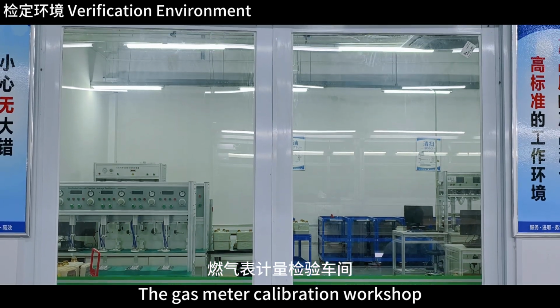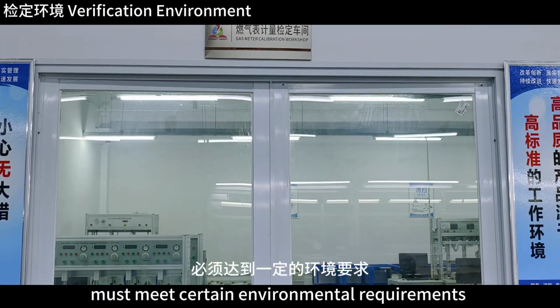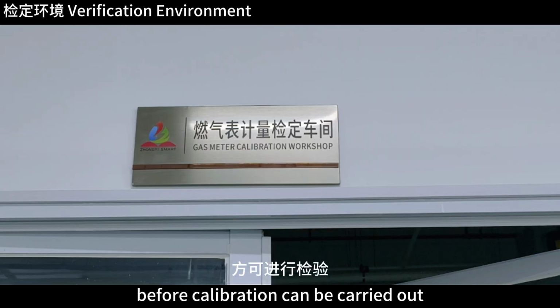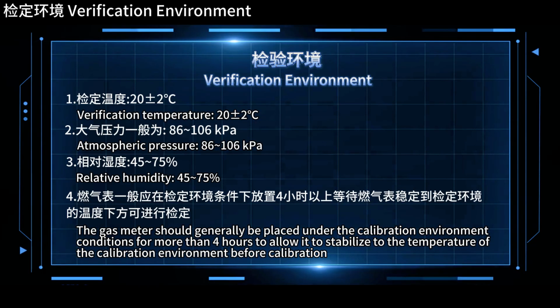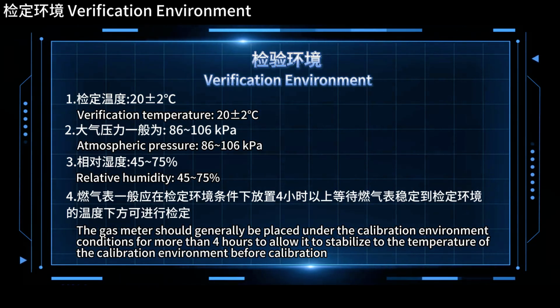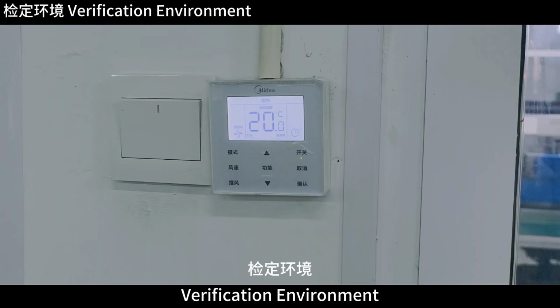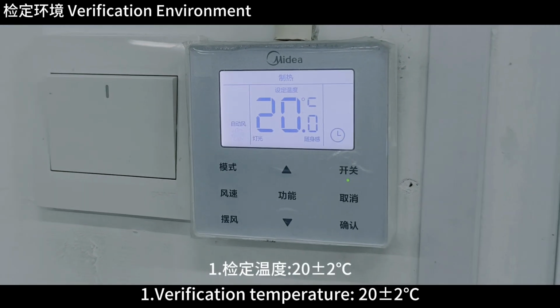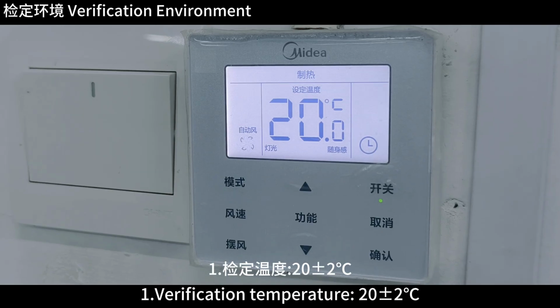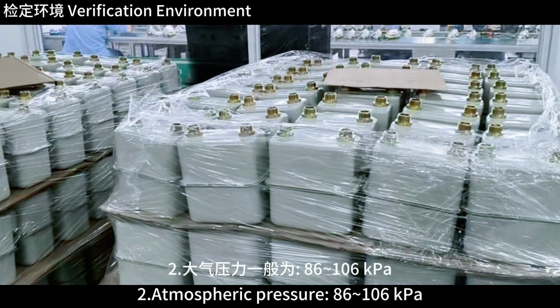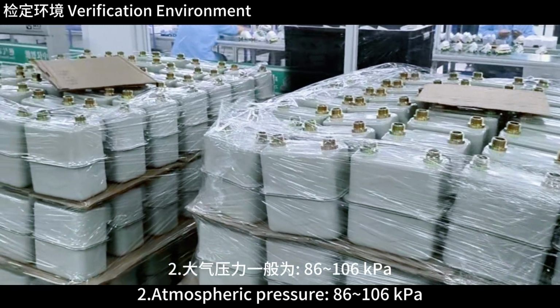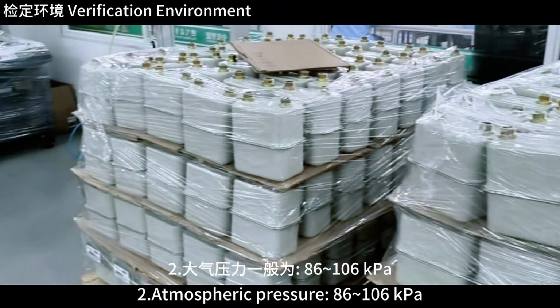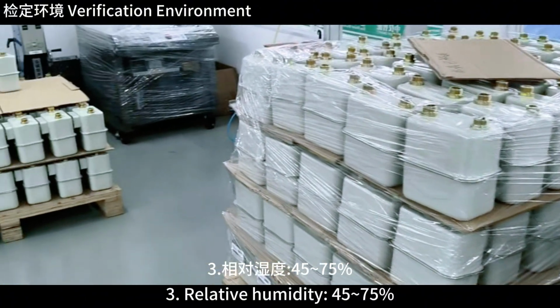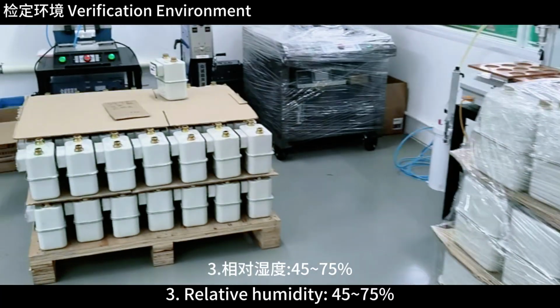The gas meter calibration workshop must meet certain environmental requirements before calibration can be carried out. Verification environment. 1. Verification temperature, 20±2 degrees centigrade. 2. Atmospheric pressure, 86 to 106 kilopascals. 3. Relative humidity, 45 to 75%.